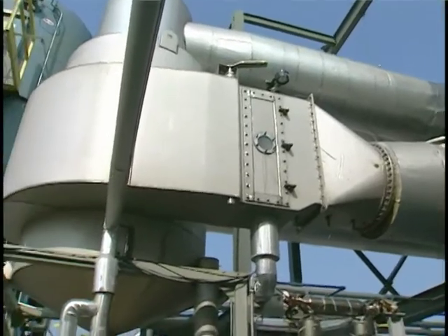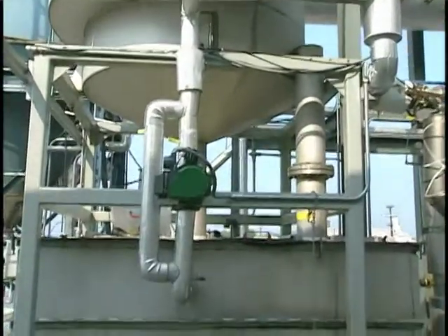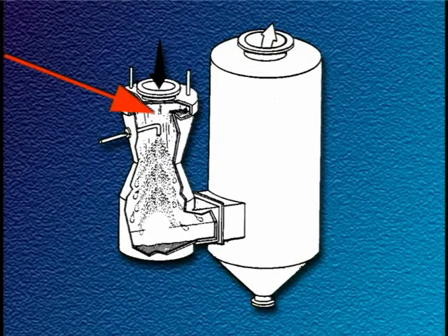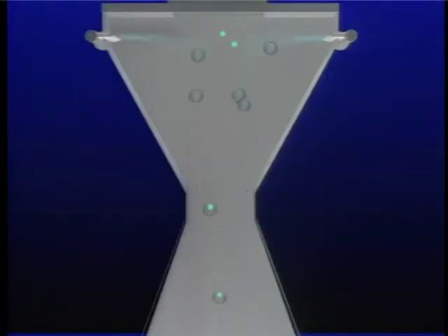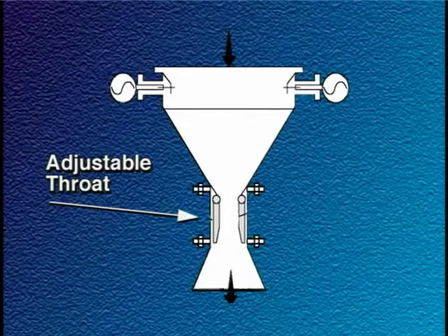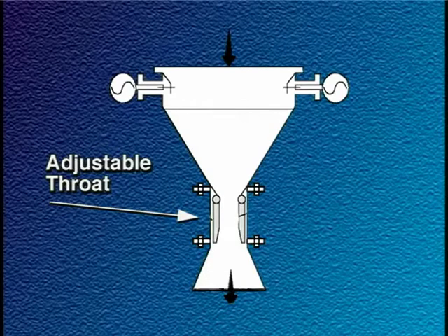One variation of the standard venturi scrubber is the wetted approach design. In this design, the scrubbing liquid is introduced at the beginning of the converging section using overflow weirs and a central spray nozzle. This is done to wet the converging section and protect it from particle erosion. Another variation is the variable throat venturi. Since the scrubbing energy is a function of the gas velocity in the throat, venturis that can change their throat dimensions are used when the gas flow rate from the process varies. The position of the adjustable throat mechanism is usually set to maintain a fixed pressure drop across the collector.